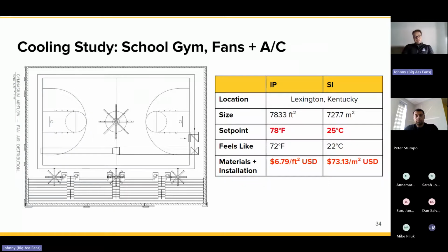So if we were to add fans in an environment like this, oftentimes what the engineer will do is cut down on those additional legs of ductwork and simply dump the air in the space and use the fans to mix. So oftentimes with the fans, you're getting 2, 3, 10 air turnovers per hour. So you really don't need all of these legs of ductwork trying to disperse conditioned air. That fan is going to push it down to where it needs to be and constantly recycle it through the space. So immediately we can see the materials and install costs actually went down, even keeping in mind we're installing fans. The set point we've raised, so we've gone from 72 or 22 degrees Celsius to 25 degrees Celsius.